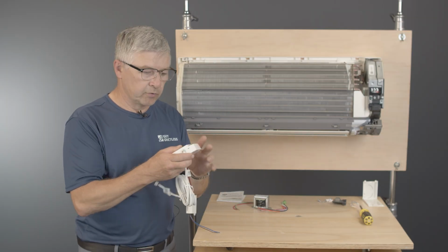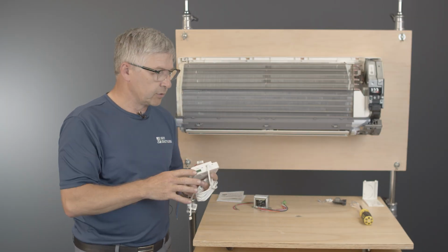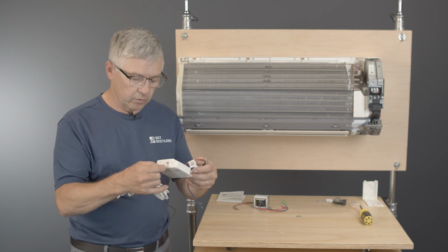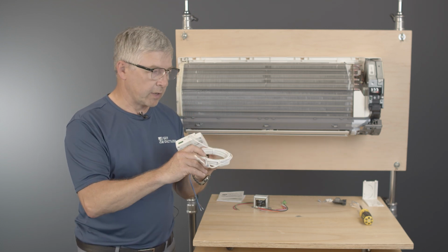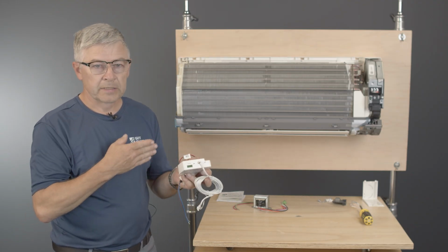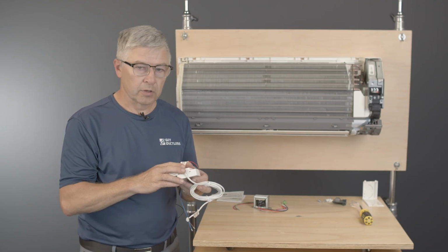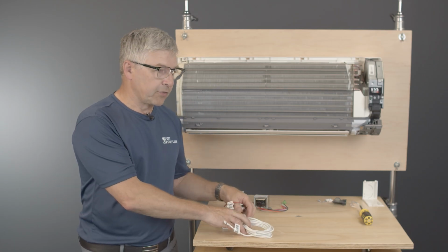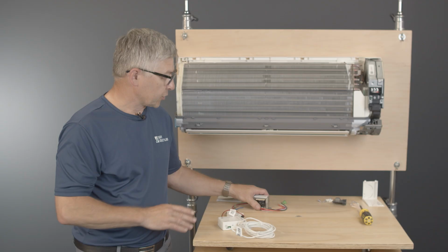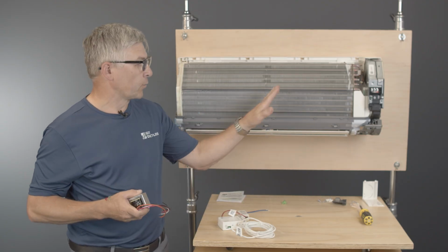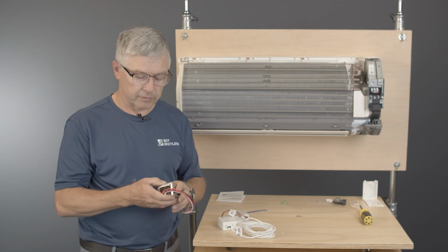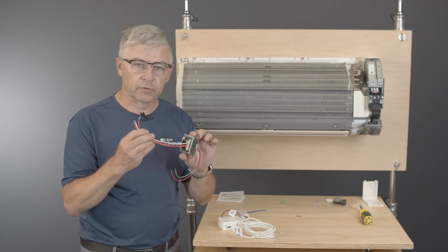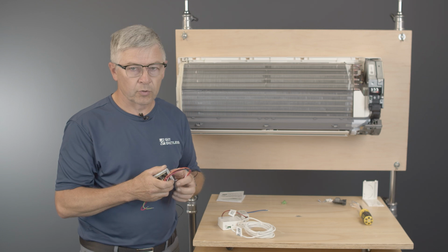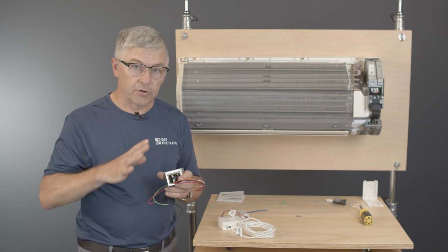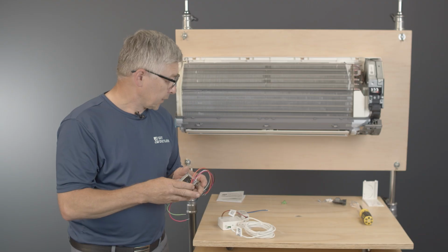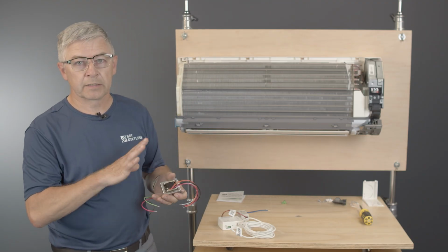So as I mentioned, if you only need Wi-Fi control for your unit or your system, this would be all that you need: the transformer, the communication wire connected to the control board, and setting up your control on the app. Now, if you are connecting third-party thermostats to control your air handler, and that's not necessarily a wall-mounted air handler, it could be different air handlers, you need the high voltage and 24-volt transformer, a control wire for the third-party thermostat, the third-party thermostat itself, and maybe an electrical junction box and access panel.